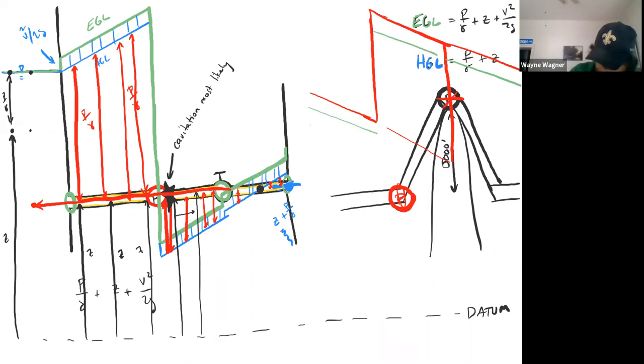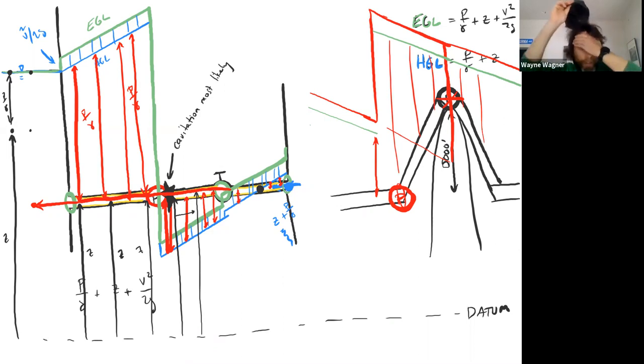And if we're lucky, if we put the pumps in the right spots, we never have to have negative pressures at all, right? But right here, notice this is a positive pressure, positive pressure, positive pressure. We always have positive pressure. So the risk of cavitation is gone. And all we've done is, but it's with the exact same pump. Because in these two things right here, HGL and the HGL are the same.